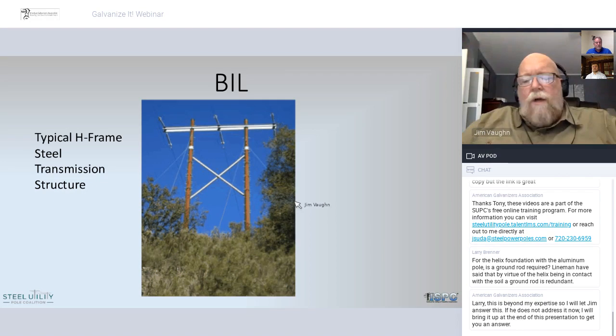pole set. There is a question that came from Larry about the Helix Foundation with aluminum pole, asking about the redundancy of a ground rod. The purpose of using the ground rod is that the ground rod itself is considered to be an electrical connection to Earth, where the helix or the grid that's installed in the ground, being galvanized, is actually a mechanical connection to Earth in order to establish the foundation for the pole. So most engineers will agree on the value of testing that the galvanized grid itself does not make as good an earthing connection as the ground rod does.